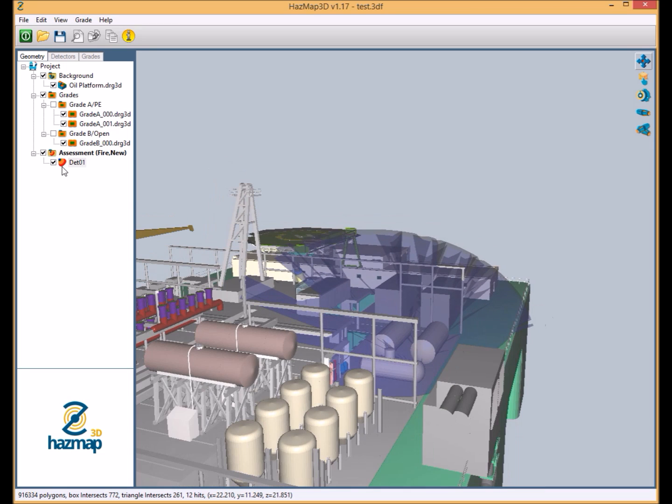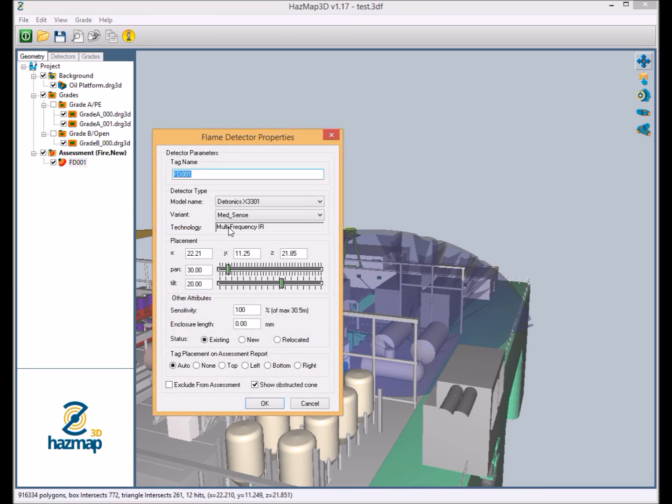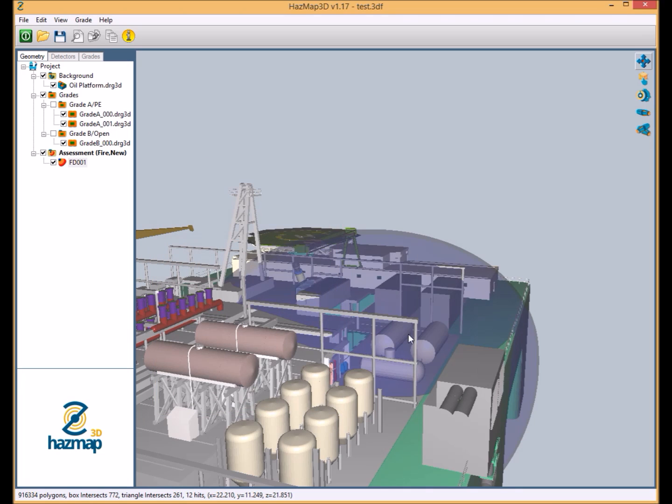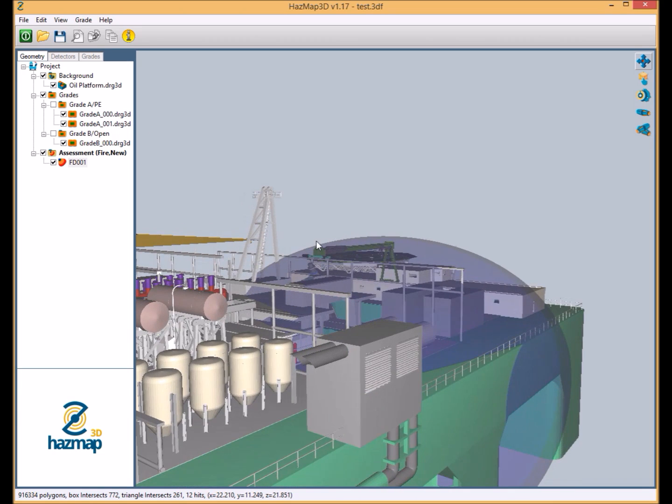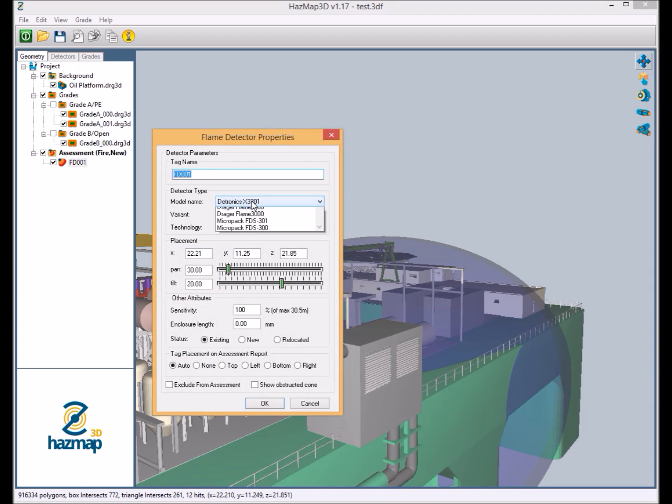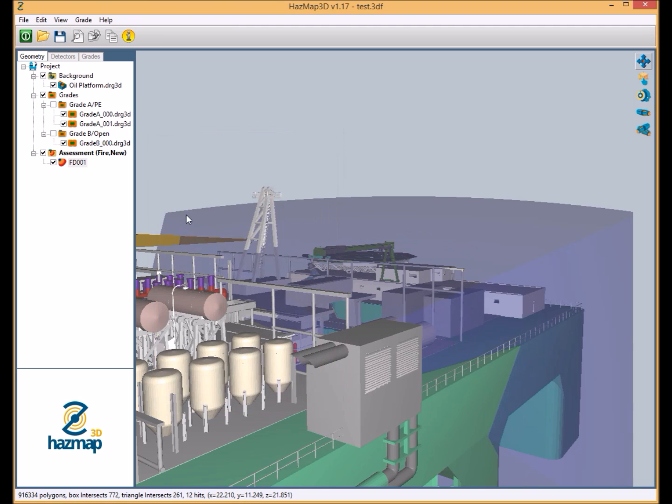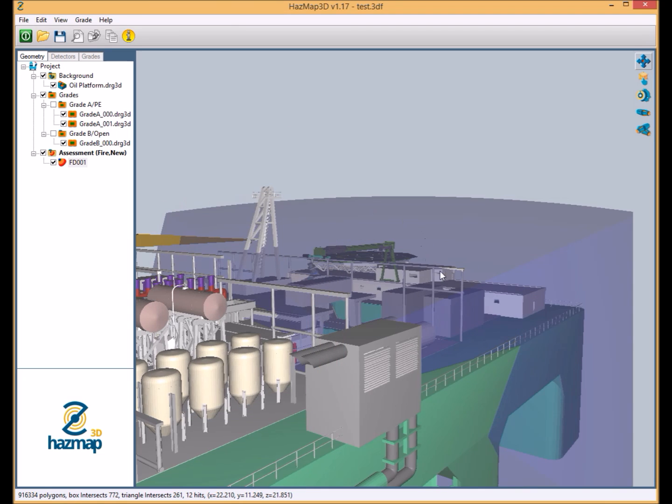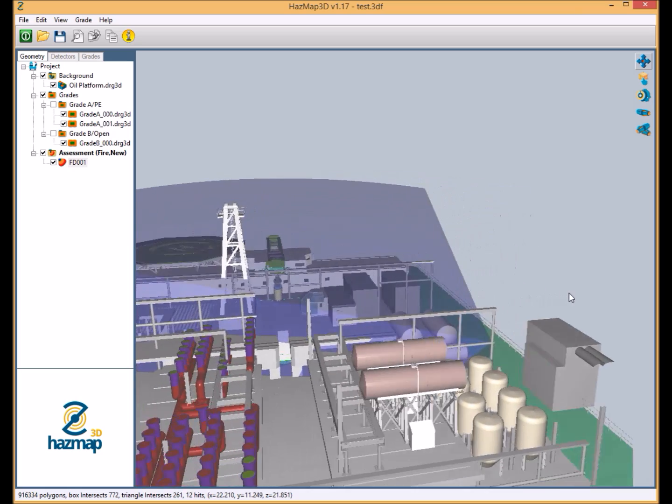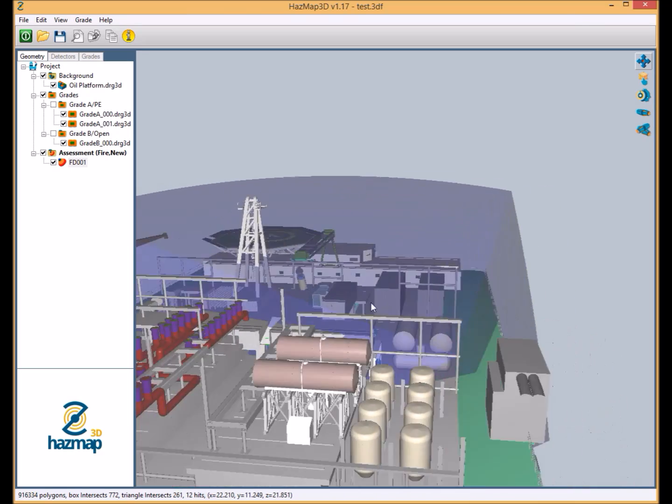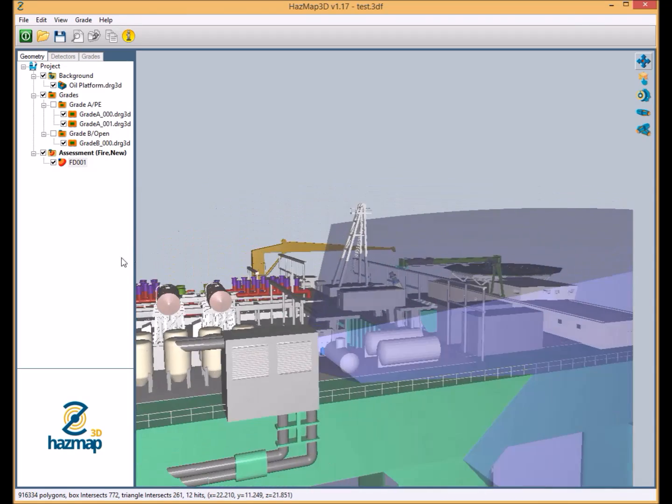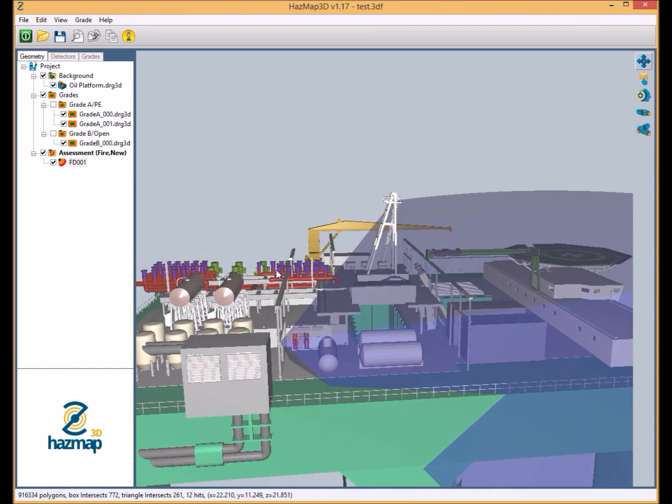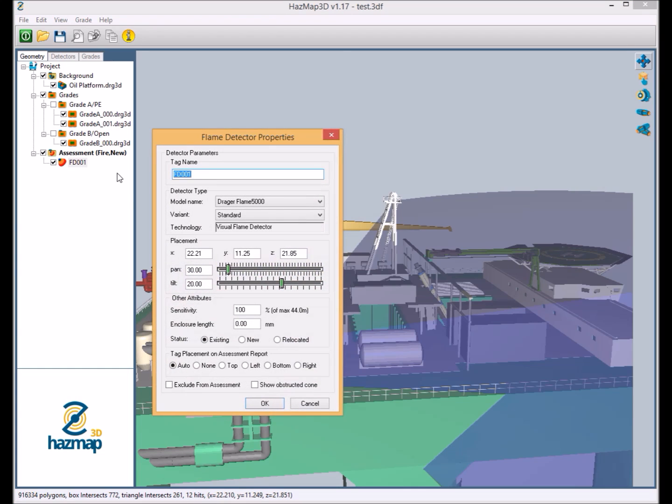But we can also see the impact of the cone that the detector provides. If we switch the obstructed cone off, you can see this teardrop style shape. If we were to change this detector to a Drager Flame 5000 visual detector, you would see that cone of vision change and it becomes more like a pizza slice shape. And this is due to the filtered edge effect of the flame detector's field of view. All of this information is completely coded into the software and independently verified by third parties.